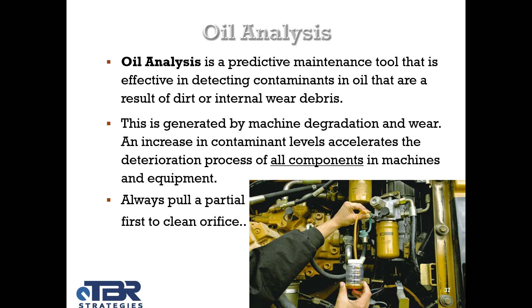Instead, we rely on things like oil analysis. It's a predictive tool that helps us identify the presence of contaminants in the oil so that we can respond and take corrective action. Because if we don't, that's going to degrade the components and degrade the performance of the equipment. One thing a lot of people don't realize is that when you're pulling an oil sample, you're supposed to generally pull two. One is a half sample, a partial sample. The other is your final sample. The partial sample is really to clean the orifice so that you're not getting any particulate, dirt, or silica into your oil sample and giving you a false reading.